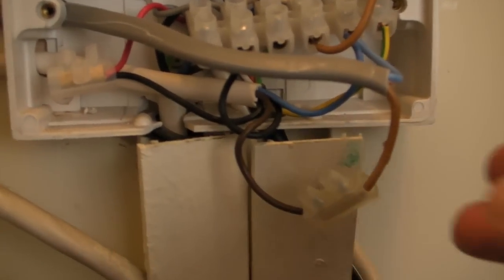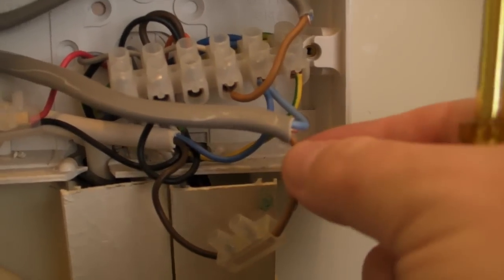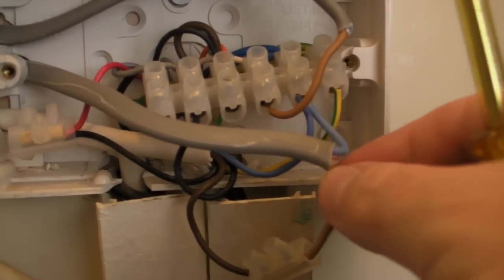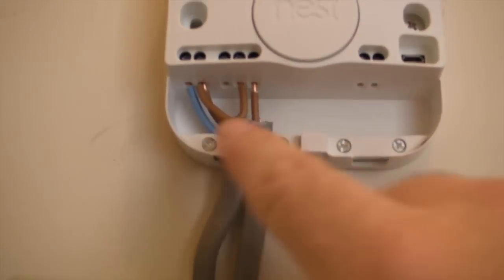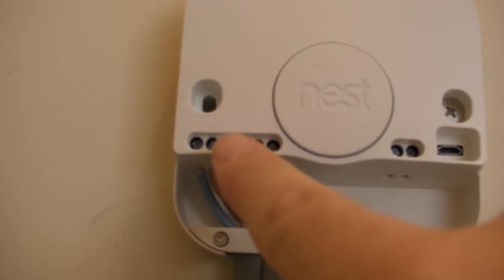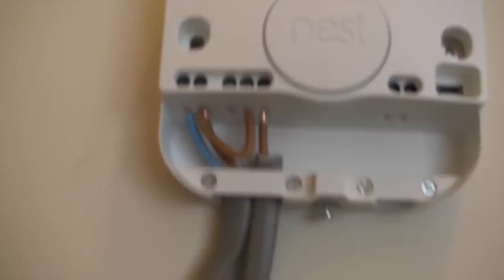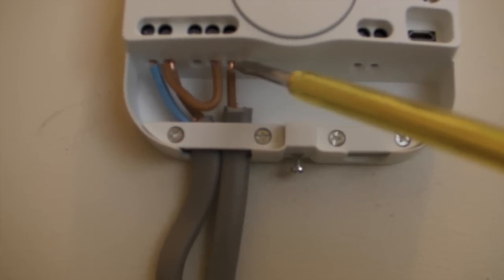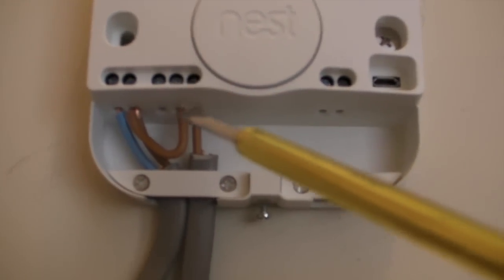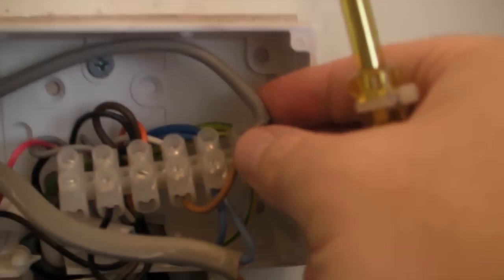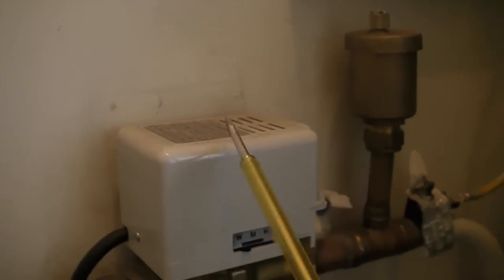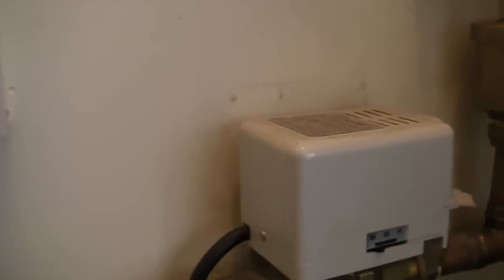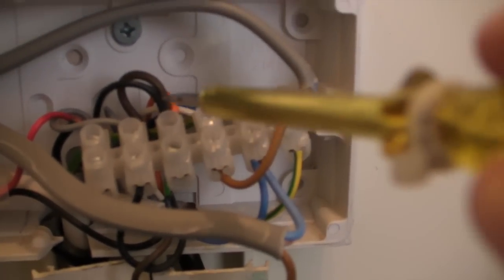So that's me wired it in. This is the main feed for the programmer, and that goes up to the Nest. This wire here goes up into live, and then I plumbed in my neutral, that goes up this wire, and that goes into the neutral up the top here, and I've still got my link there. And then number three, that gets plumbed in, that's this wire here. So that gets plumbed in to there, and it goes into the white wire. This white wire there goes into this valve, and that sends it through a micro switch, and that's what gives you your power back out into this one here, which is the orange wire, and that powers the pump.